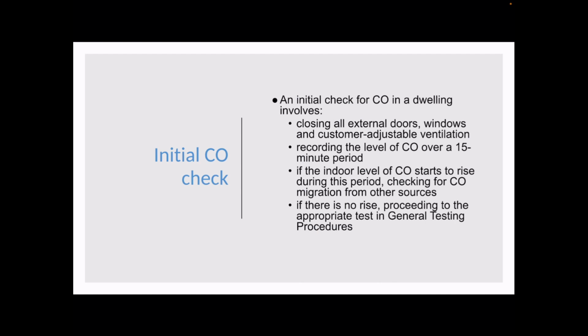So when you've got there and you need to carry out your initial carbon monoxide test, you close all the external doors, windows, and what ventilation you can, and you record the level of carbon monoxide over a 15-minute period. If the indoor level of carbon monoxide starts to rise during this period, check for carbon monoxide migration from other sources.